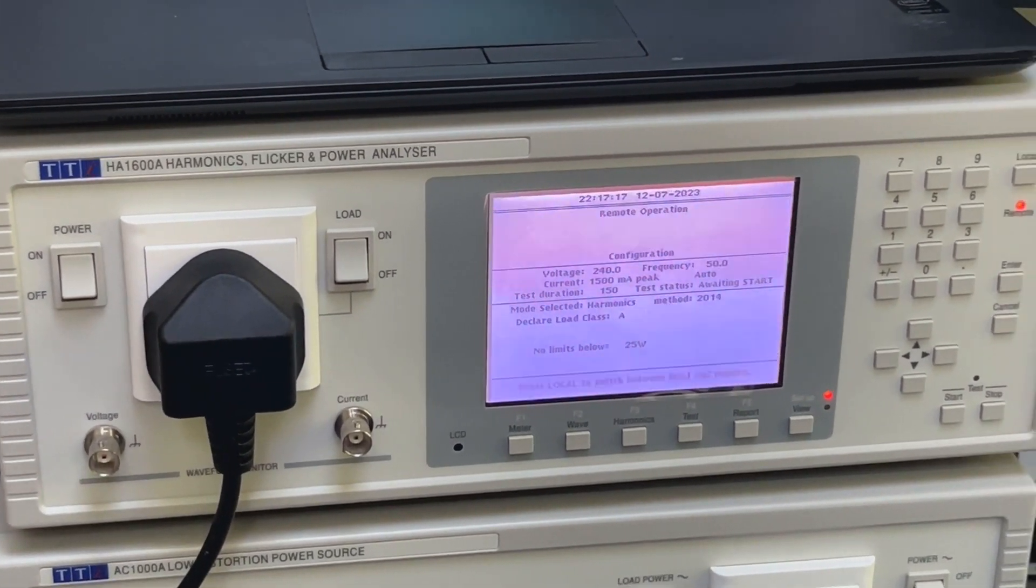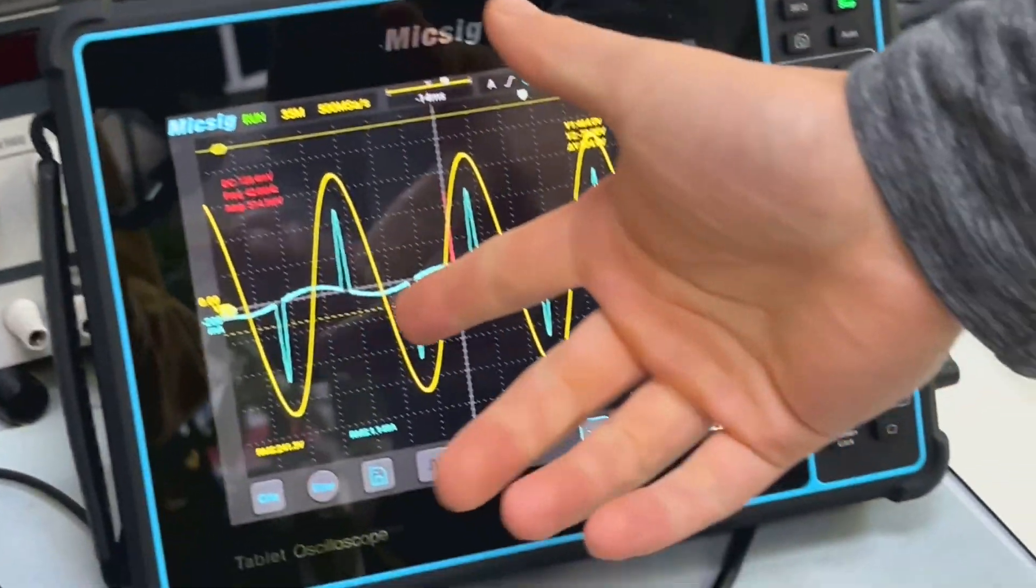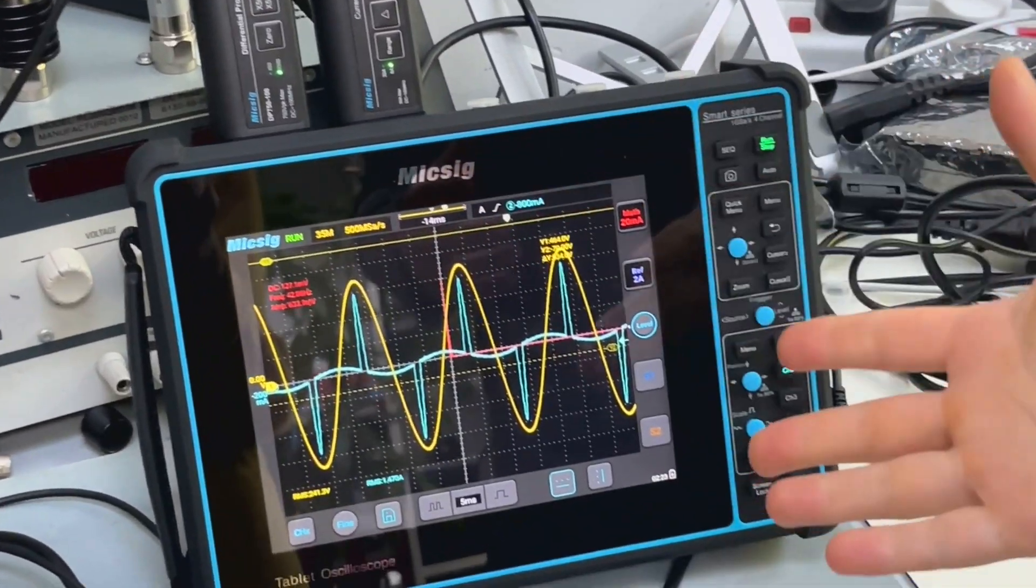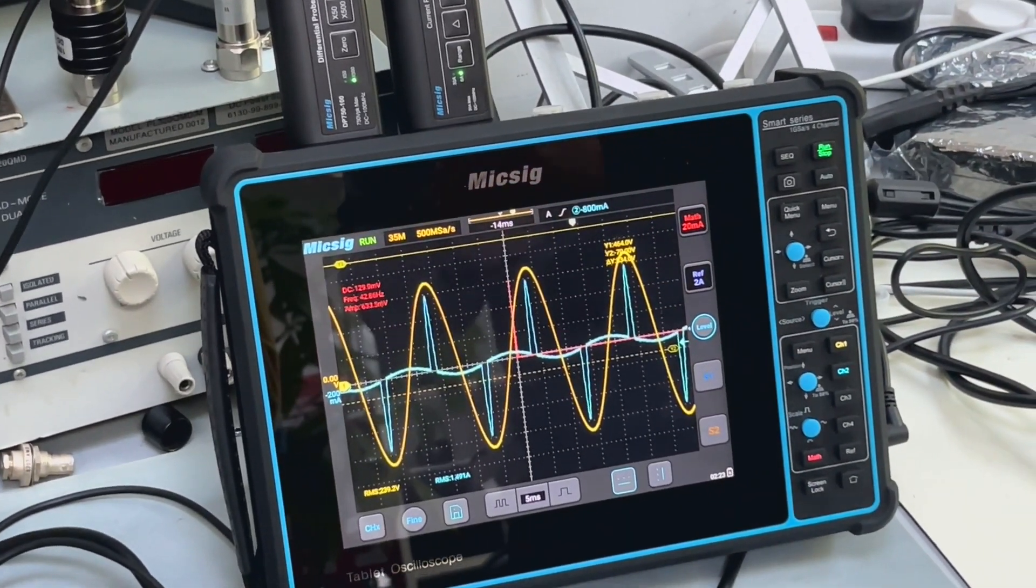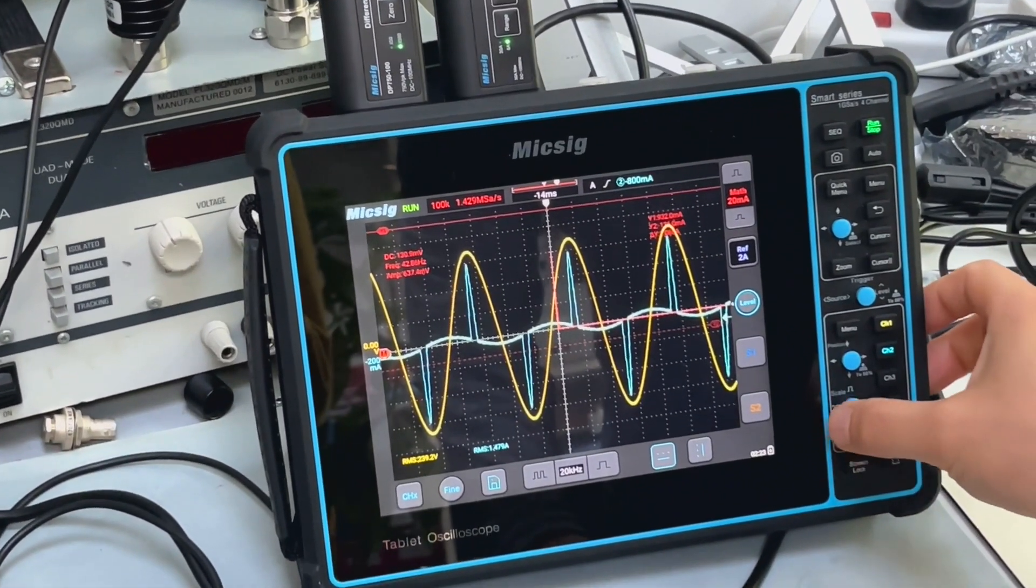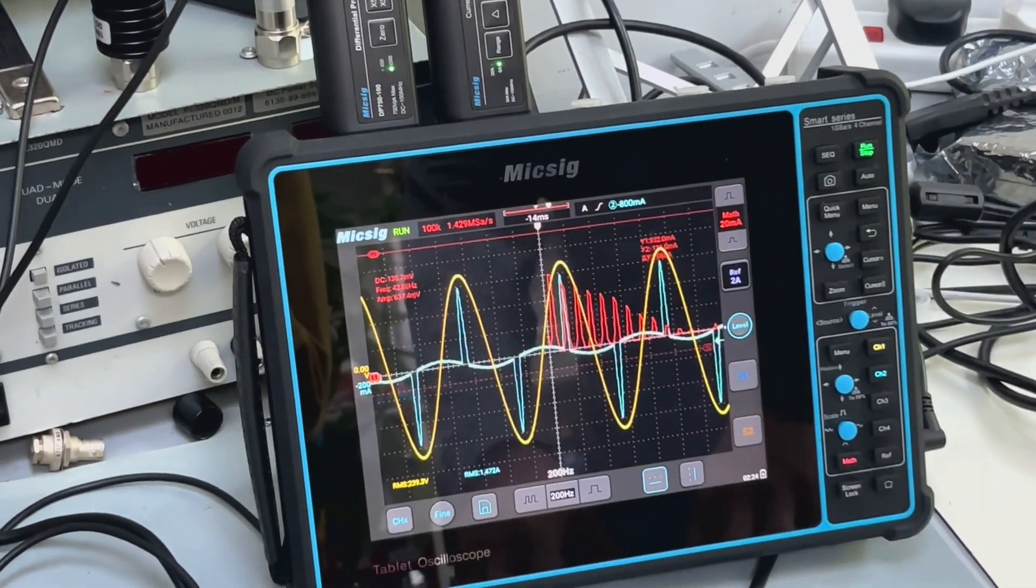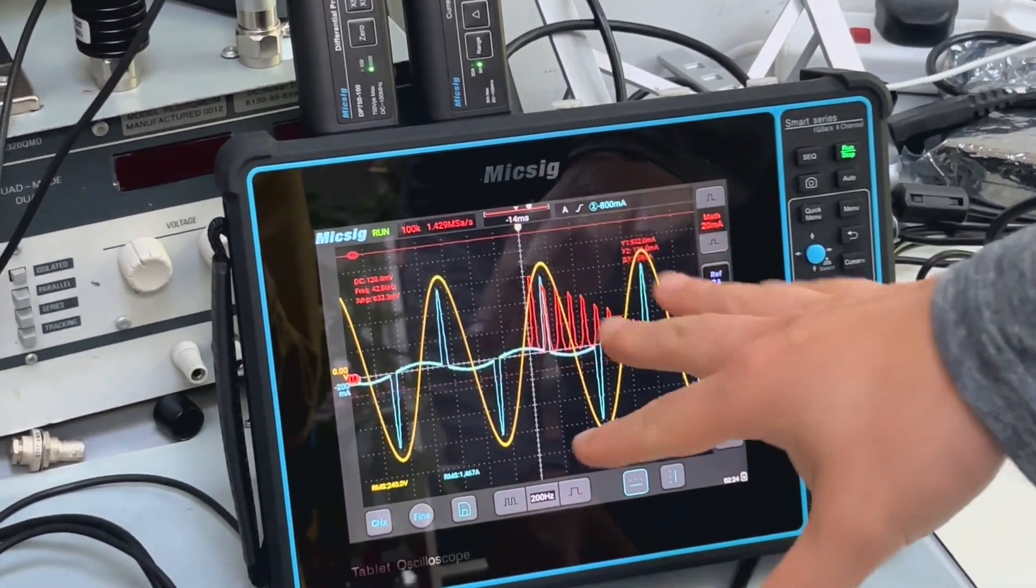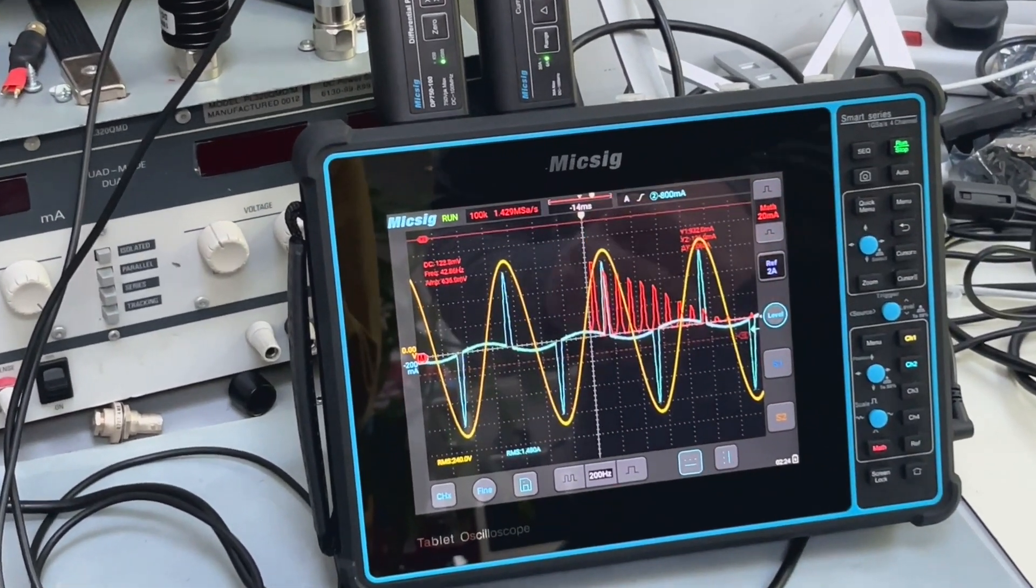So with this in mind now I'm switching on the unit again. So as you can see here again we have a very clean AC voltage. But the current of course is definitely not sinusoidal in this case. Now if I click math and I believe I can zoom in, so you can see the red trace here shows you the harmonics content based on a very simple FFT analysis of the current waveform.